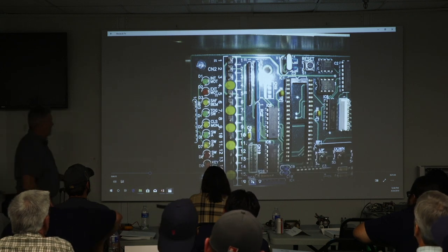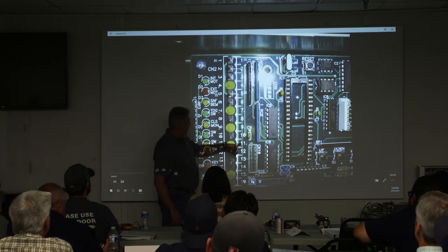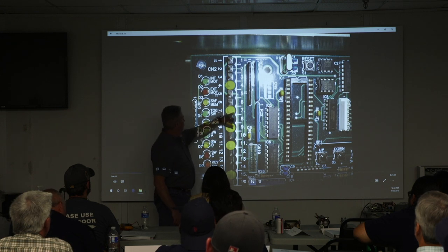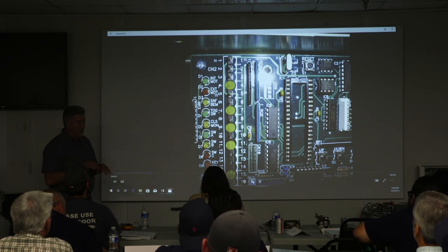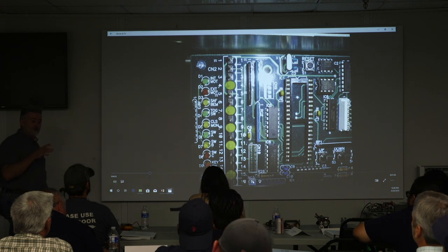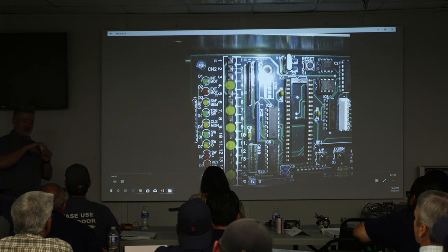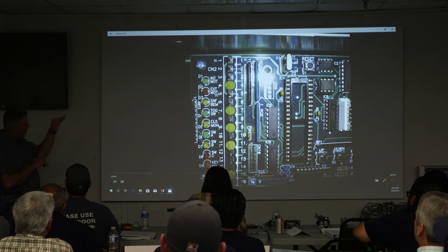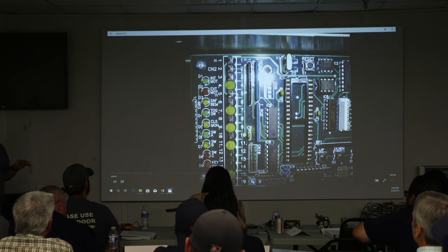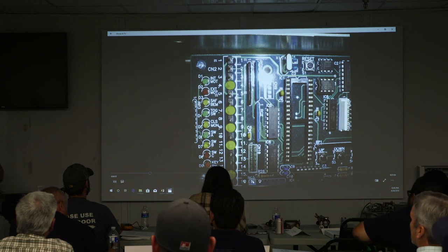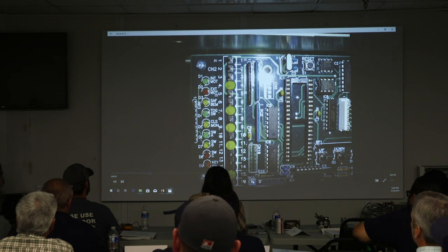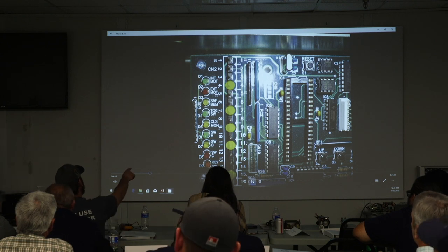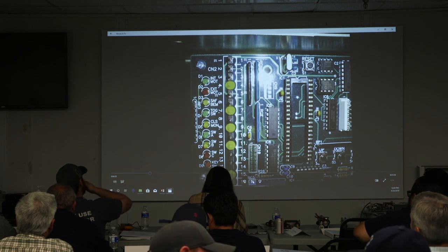So when you see that period back here, behind it, number 11, 9, 7. What I have seen guys do is they'll take one large wire that's about 6 or 8 inches long and land it under number 11, say, and then they'll bring all their commons to that, and land and jump everything to just that one. So all of them are the same. And so they can bring all those commons from the motion detectors, everything into that one, put it under one wire cap. Yeah, we do that when you've got bunches of it. So anything with a dot at the end of it is a common. That is correct. Okay.